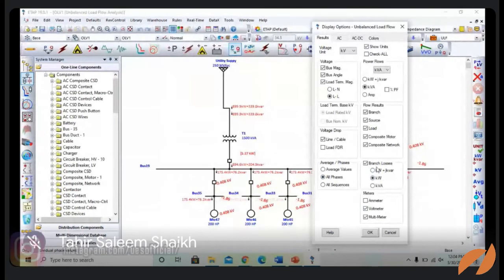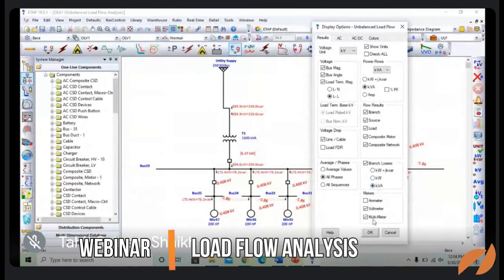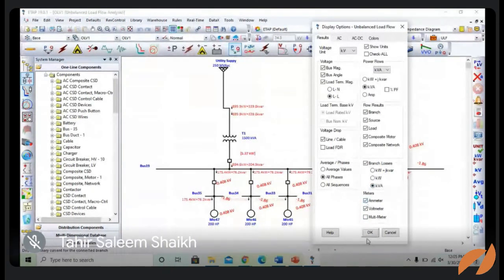Okay, now branch losses. If you want to know the reactive losses and the real power losses, then you can select this one, kilowatt plus j kVAR. If you want to know the S, that is the apparent power losses, the total losses, you can select over here. Now for the meters, you can also select the Multi-Meter over here.